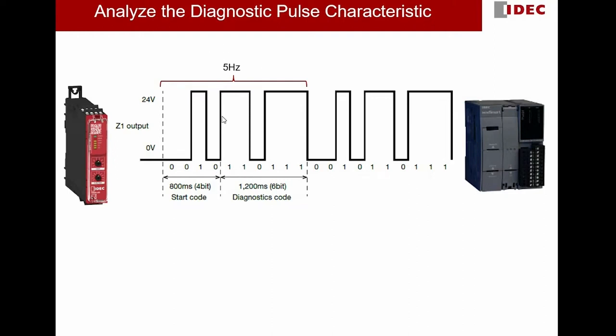How do we get 5 Hz? If you do a simple calculation, these 10 bits require 2 seconds of period to complete. So that means in one second it will have 5 bits, which means it's 5 Hz. This diagnostic pulse cycle keeps repeating itself — one cycle is followed by another cycle and so on.